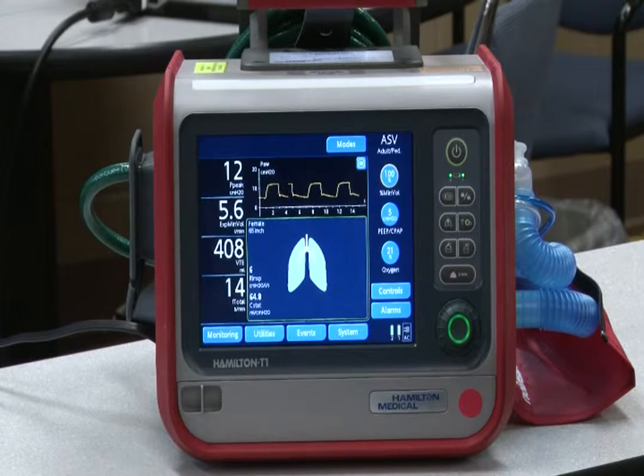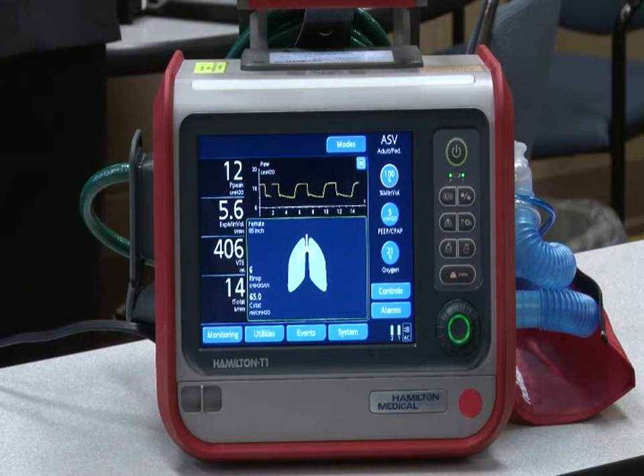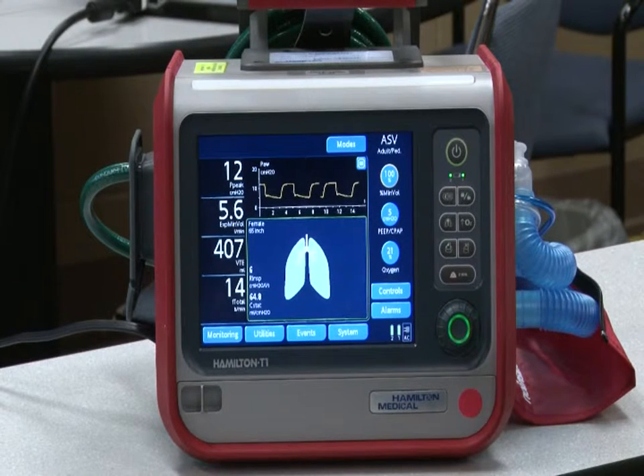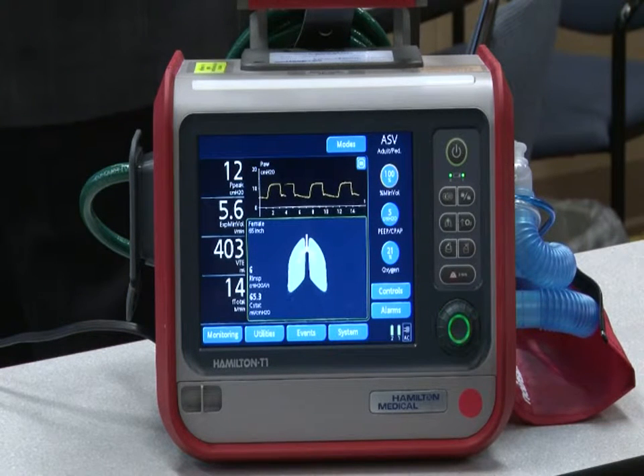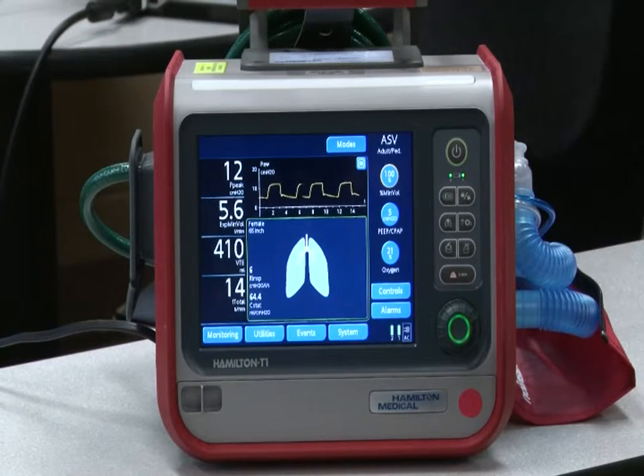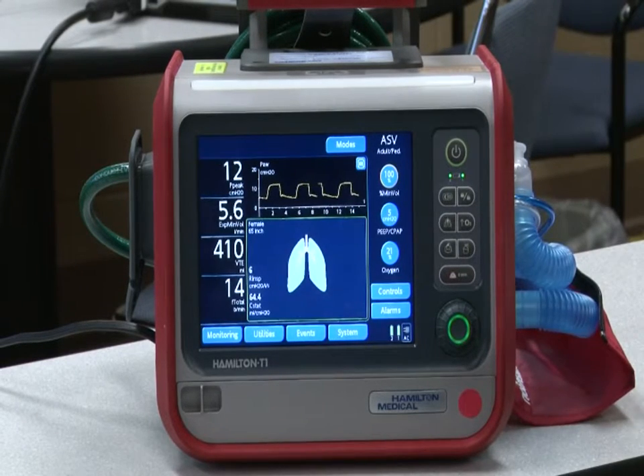And then the picture depicts that based on an average of 8 breaths. So these update breath by breath. This is an aggregate of 8 breaths, and it's referenced and compared to what would be normal in the normal range. So compliance isn't a number, it's a range. Resistance isn't a number, it's a range. And it moves up and down based on ideal body weight. And if the values are within the normal range for a patient of that gender and size, you get a little green pencil line around the display. Yours does not have a green pencil line around the display. Okay? So we can just stay on that because we're going to do a bunch of stuff with that. If you would, please. Thank you.